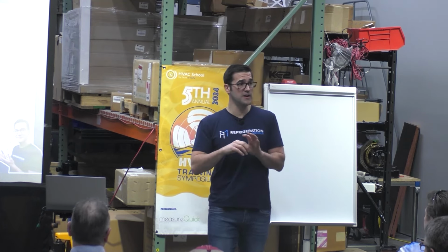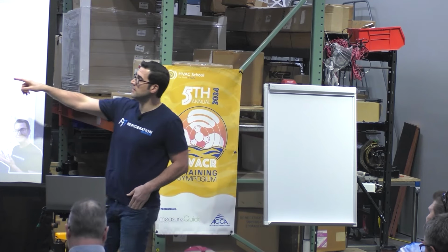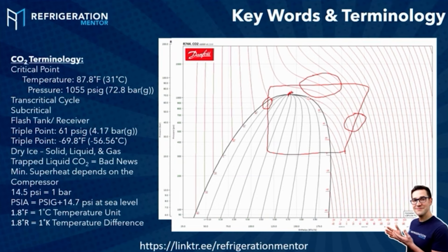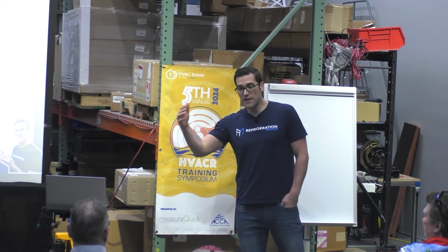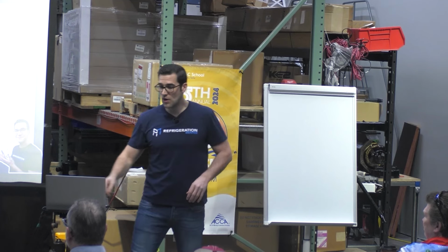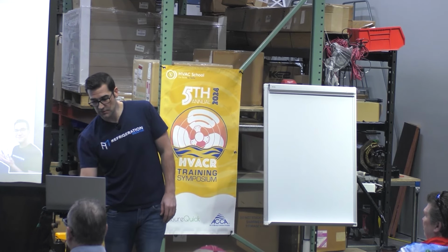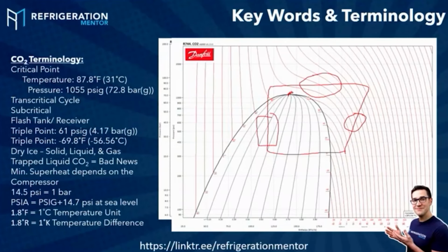Have everybody following me so far? Okay. So we get to this metering device, and what it does, it takes a pressure of potentially 1100 PSI, 1200, 1300, 1400, 1500 PSI, and reduces it down to 500, 550 PSI. Some people might be using different units. Okay, 100 bar down to like 34 bar, for the people online. So what this metering device does is get it down, and it drops into our receiver, which is called a flash tank, which is the next term on there. Flash tank receiver, as you can see there.